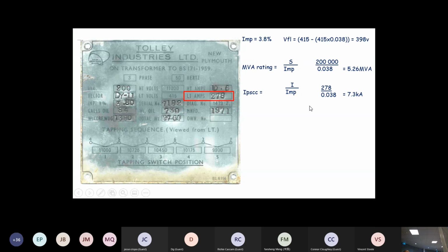Now, could you remember I said to you that S equals √3 times V times I? If I was not given I, can you say I equals S divided by √3V? It's just to transpose the formula. Now this is the same. So ignore the impedance for now. So S divided by √3V. Isn't that S divided by √3V the same way to work out the amps of 278? And you divide that by the impedance. So the 200,000 volt amps, which is given, divided by √3 times 415, and believe it or not, it's the same bloody answer.